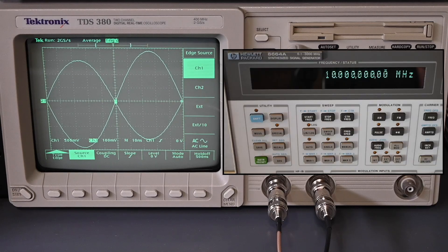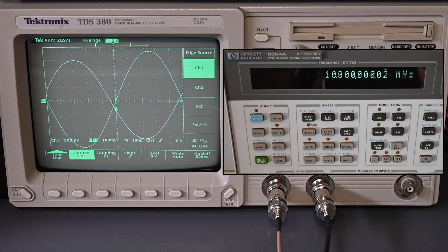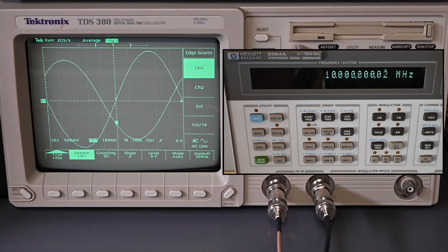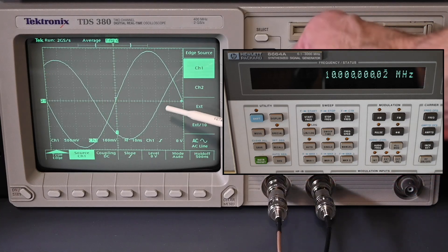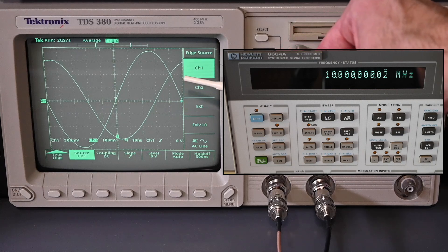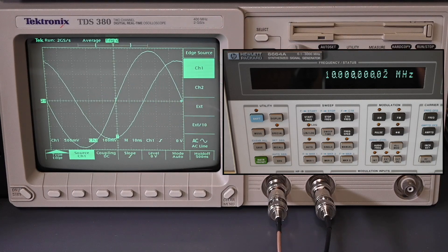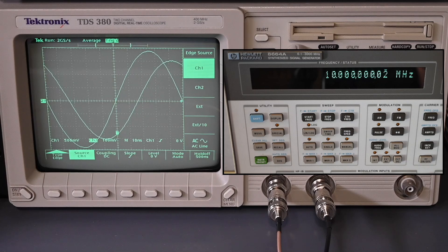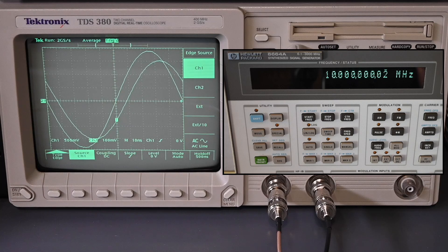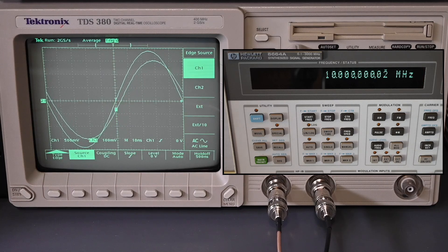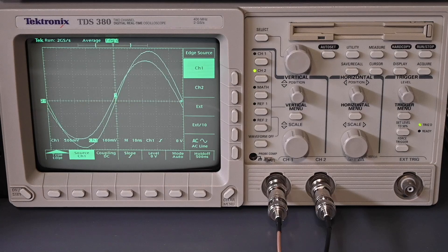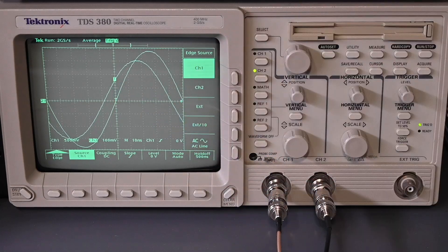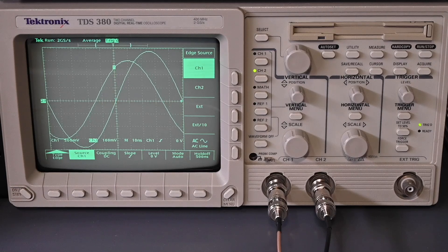So if I go over to the signal generator, I'm going to increase by, I'll go up 20 millihertz. Okay, so it's 10 megahertz, and then I increased it by 20 millihertz. So very small increase. But look at that. Now the signal generator's waveform is drifting just a little bit to the left. So now you can see that the waveforms are changing with relation to each other, and you know that the frequencies are not exactly the same. So when I was adjusting the time base oscillator, initially, it was moving a little bit faster than that even. So it was a few tens of millihertz off.